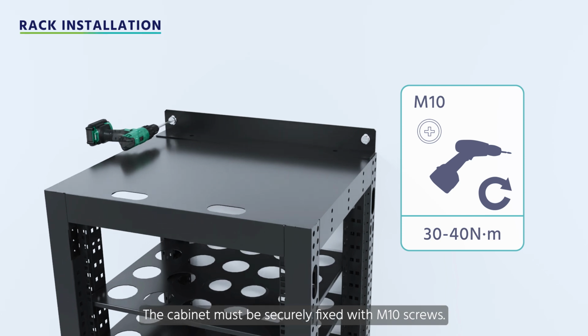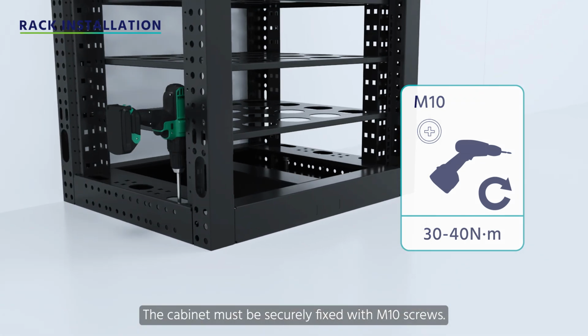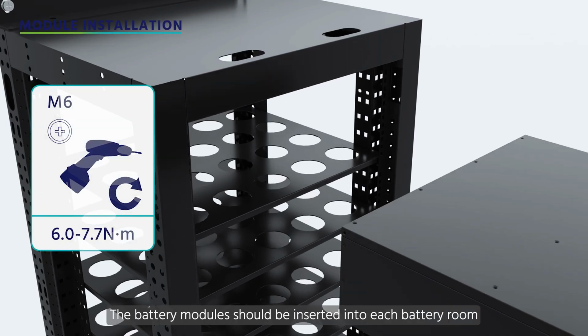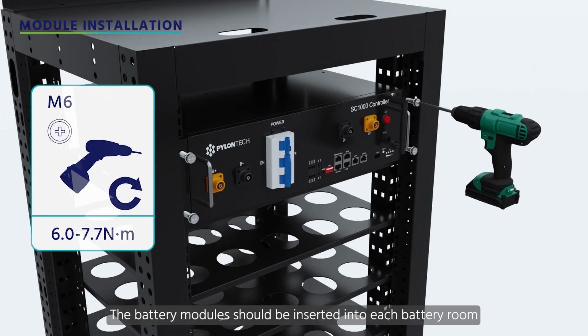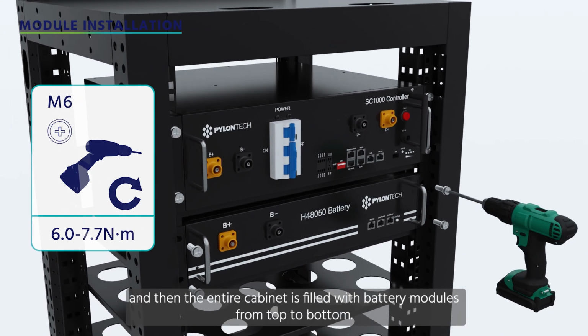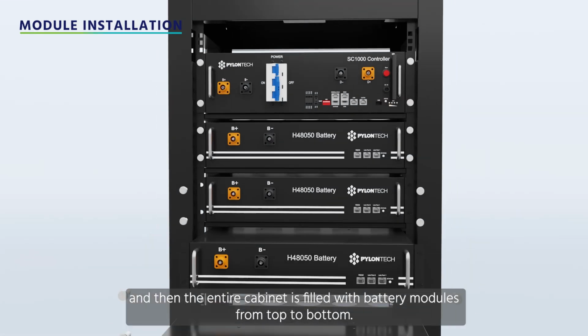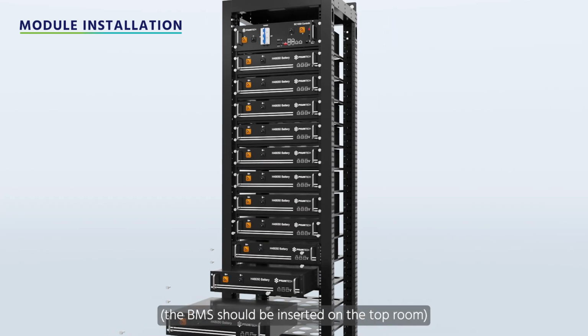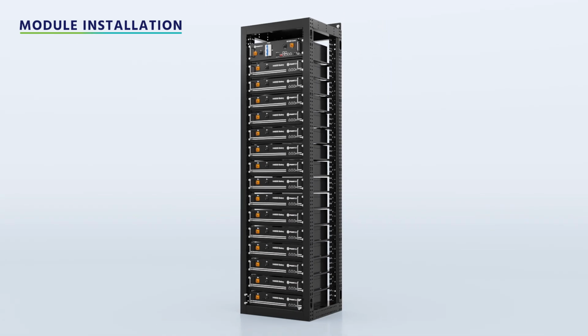The cabinet must be securely fixed with M10 screws. The battery modules should be inserted into each battery room and fixed with 4 screws, and then the entire cabinet is filled with battery modules from top to bottom. The BMS should be inserted in the top room.